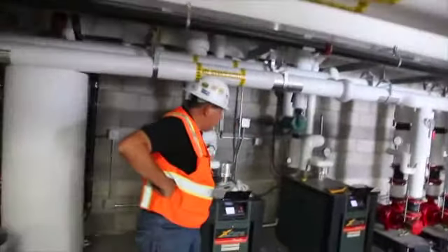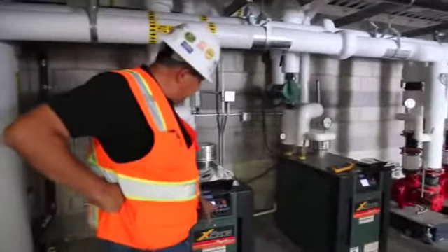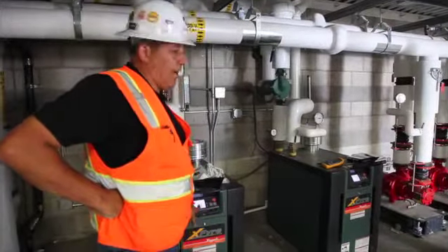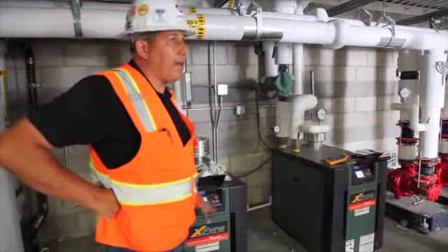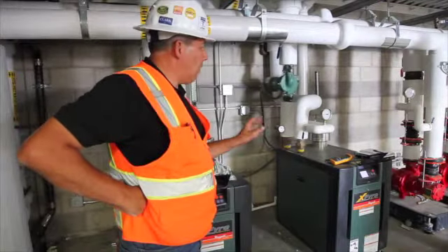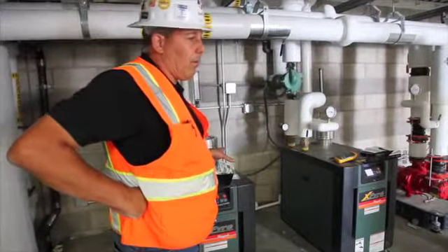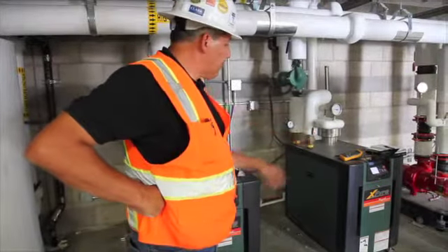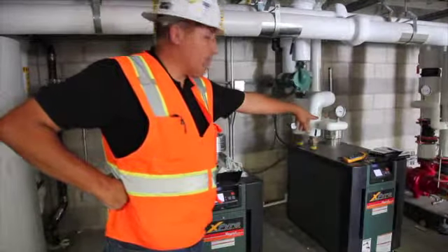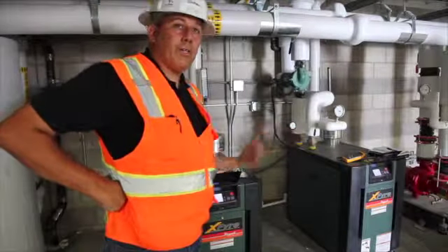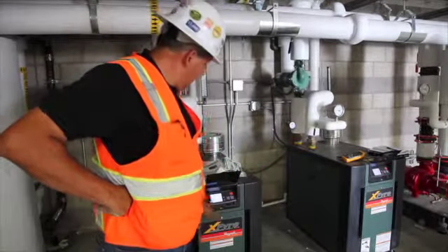You can disable a boiler. This is the master. The reason why it's a master is because on the controller there's a dip switch that tells it it's the master, and everything beyond it has to be a slave. So this has a particular dip switch number 2 on, that has the one off. So this boiler, even if you turn it off, will still run the lag boiler on its own control, because it doesn't see the communication any longer. Okay.